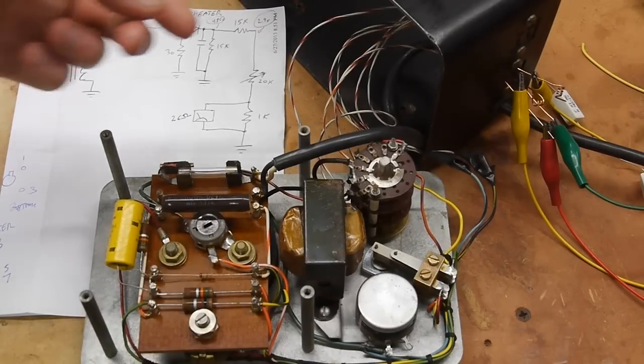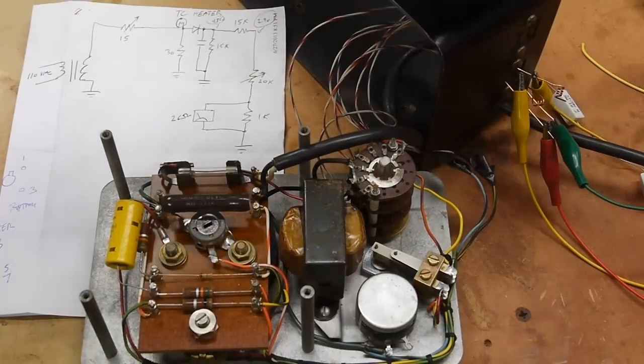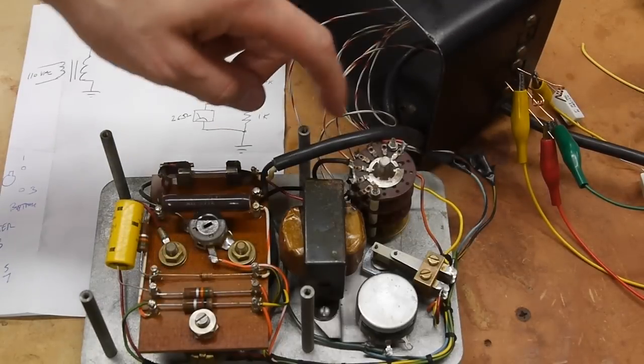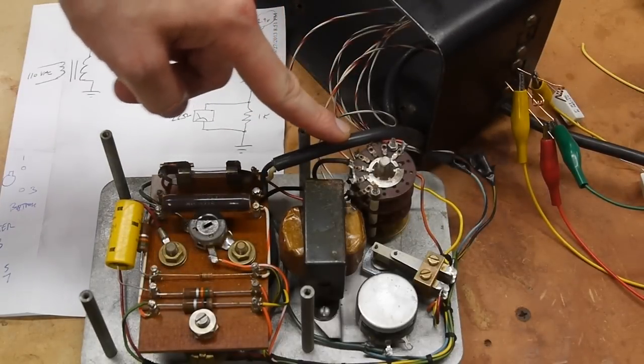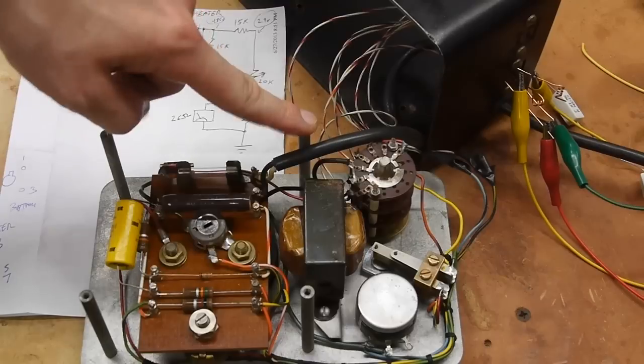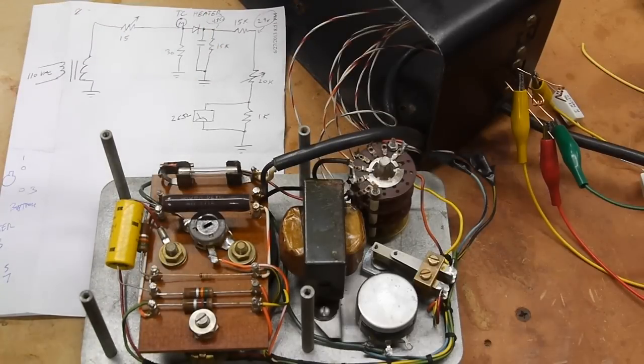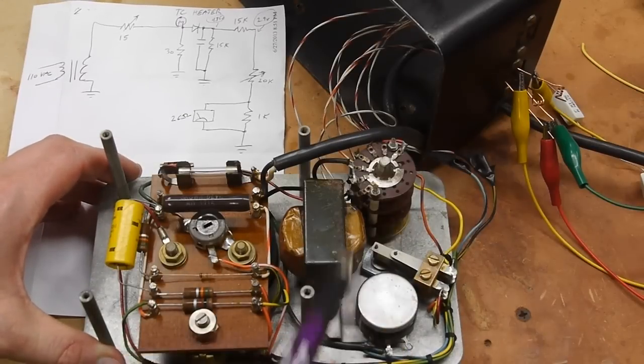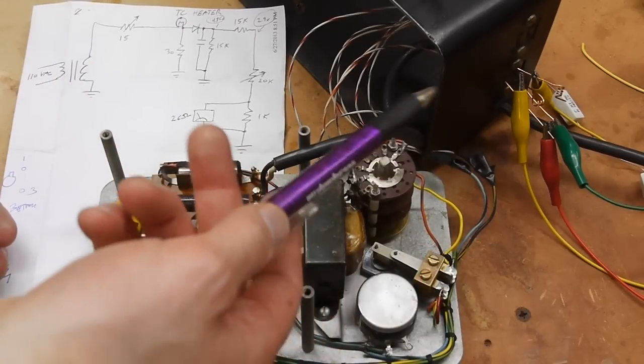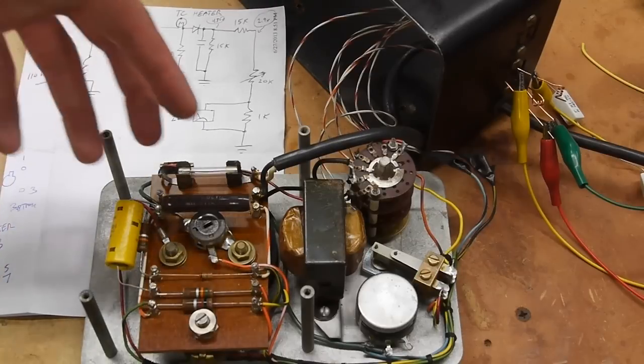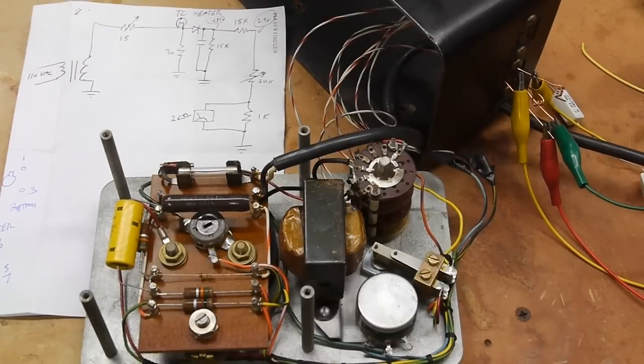So I imagine when this device was originally set up it came with a bypass plug. There aren't enough positions on this knob for it to switch the current to both sensors. The return path is dead simple. The other two sections of this knob just switch the return from the thermocouple directly into that analog meter. That's why it works with the power even switched off.